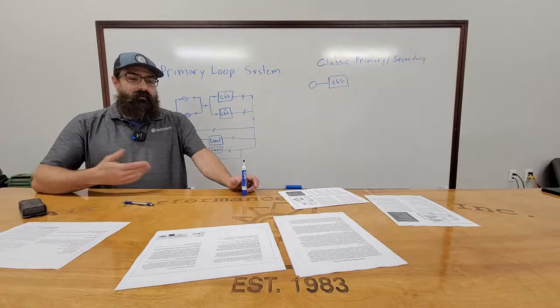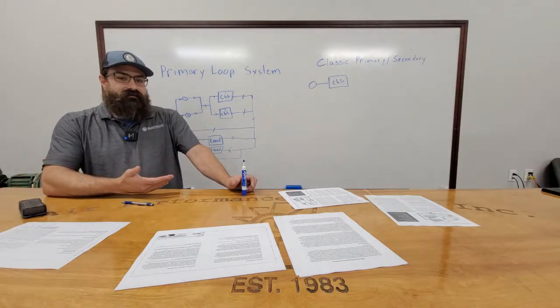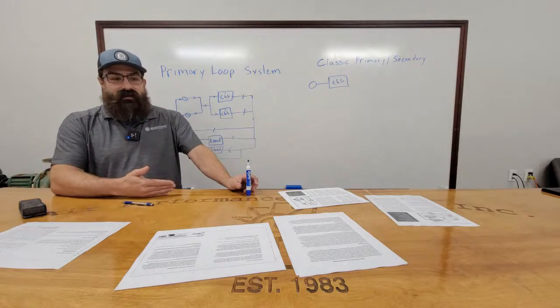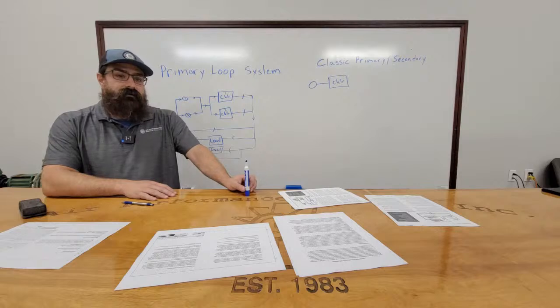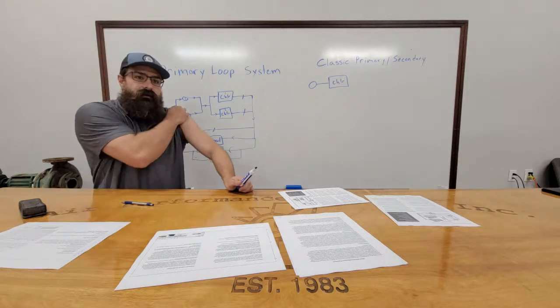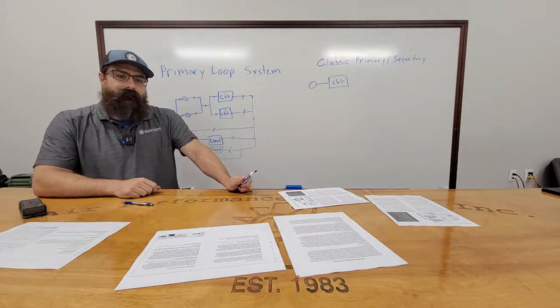So that's why we have to run both pumps to maintain the differential on these coils. Because when you look up the manufacturer's info on the coil, it's like an 18 PSI differential is what they want. And the only way I can maintain that with how the building is set up is by running both pumps at full speed. It will not do it otherwise. I had that happen, and they ended up putting just smaller booster pumps right at all the coils. And then they were able to shut off the two, I think they were like 60 or 75 horse, and throttle those back down. They used smaller pumps, like B&G series 80s or 100s.